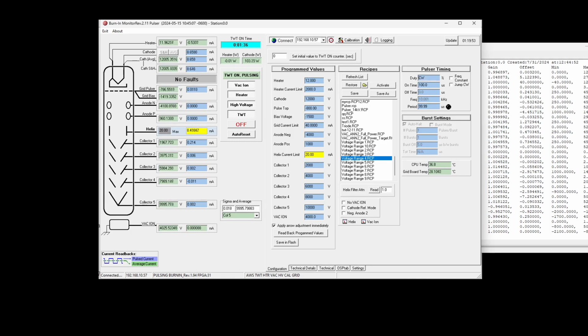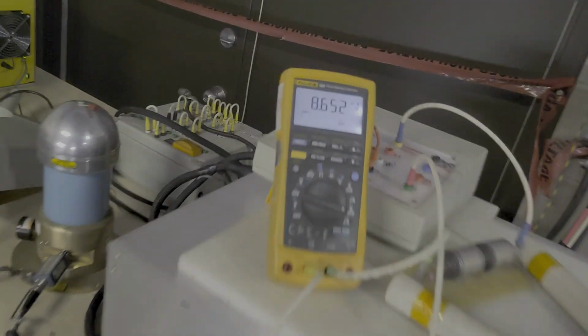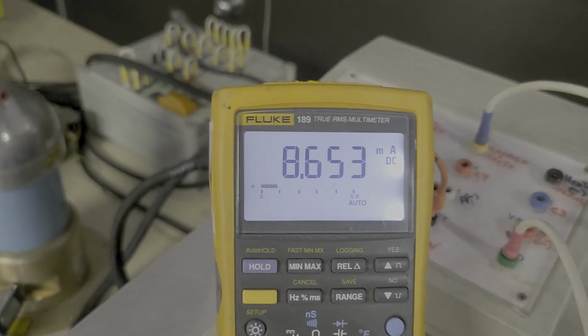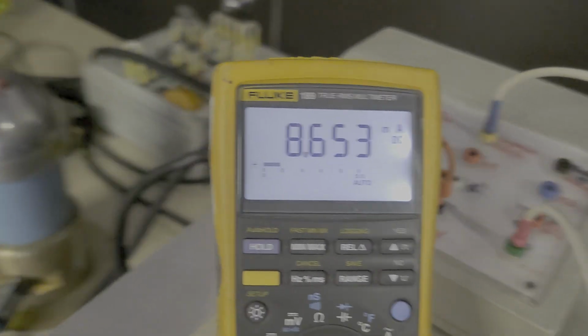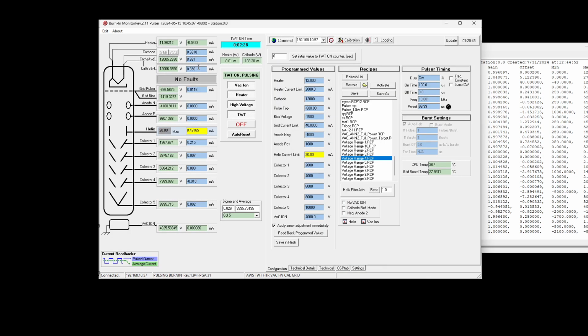Let's also set this to 100, just for the sake of consistency, so that we see on our sample and hold current, the cathode is equal to the average current. So let's head over there and see what the meter says. And we had 8.65, and we see 8.65 milliamps on the cathode, which is exactly correct. As you recall, cathode already reads 8.65 in the GUI, which means it is calibrated. So we've verified that cathode is calibrated.